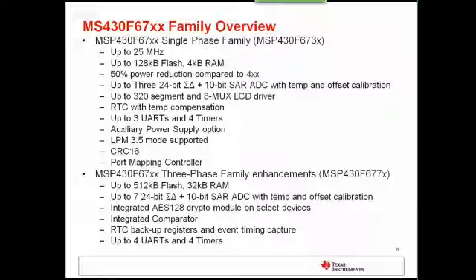One other important module of the 67XX family is the AUX module, and this allows you to power the meter from an alternative source than the one connected to AVCC or DVCC. So for instance, the use case for this is whenever there's a power outage, you can still run the meter off of a backup battery.